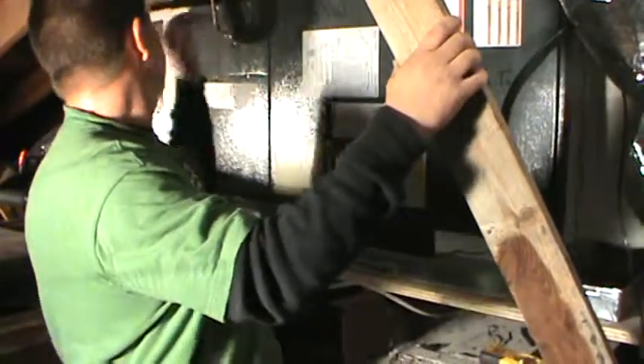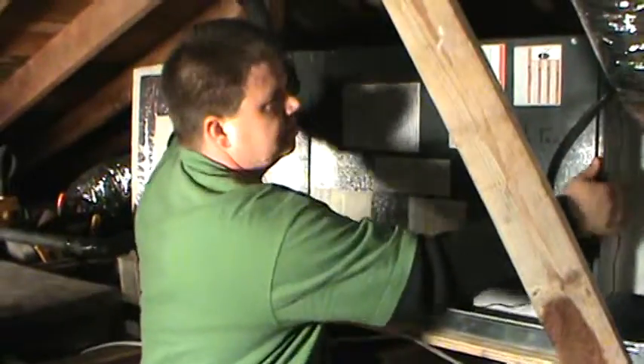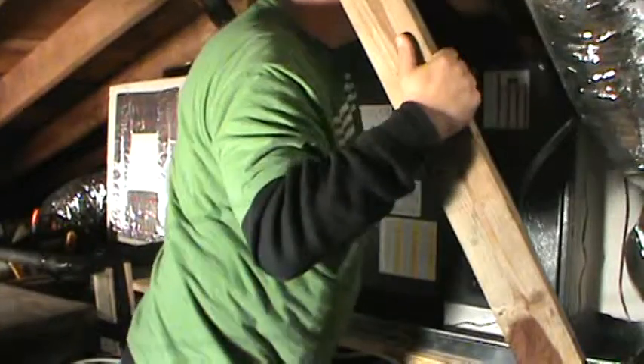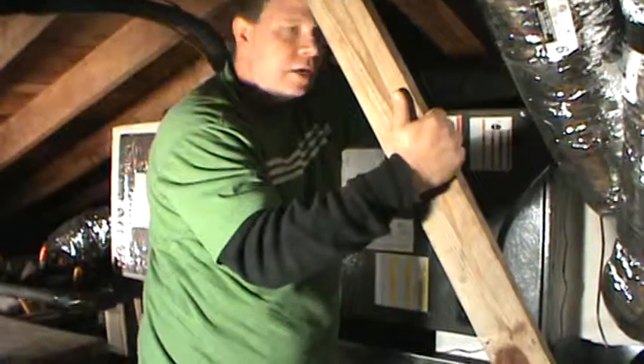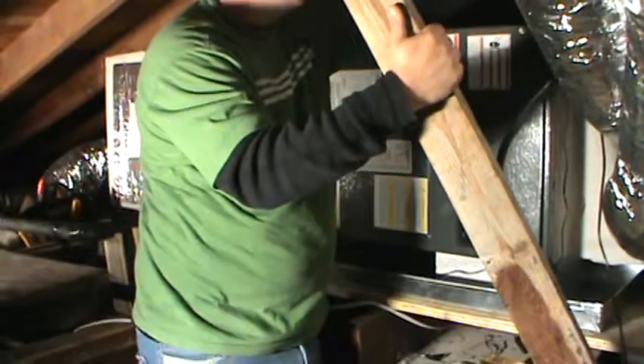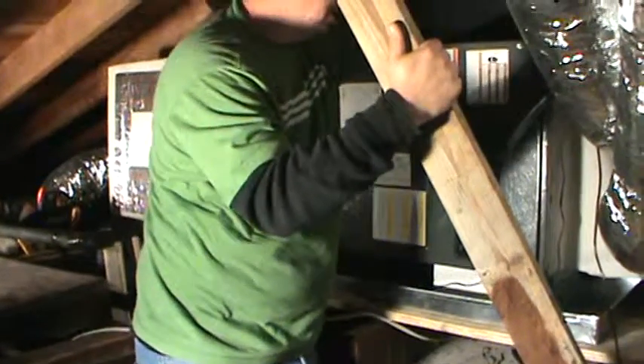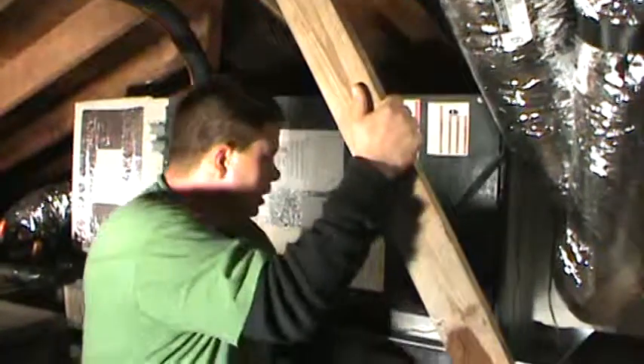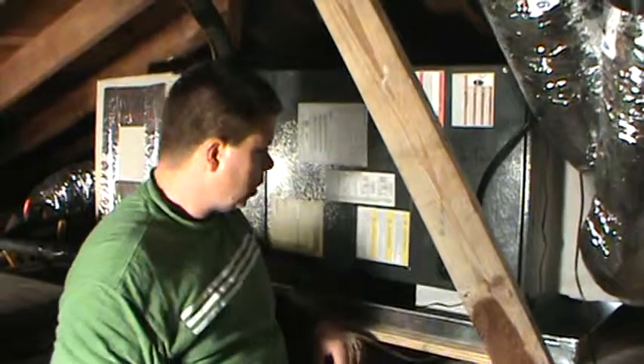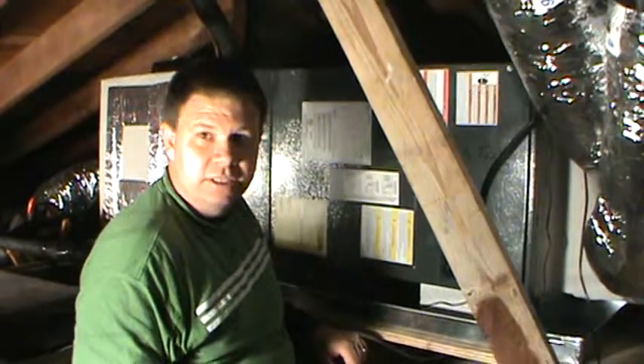Of course, you want to make sure your connections at both sides of the unit are good too. That you don't have any leaking. If so, spray glue, tape that down. If you have some mastic, mesh and mastic is great too. That'll make sure it stays on there. All right, we'll go down and start the unit up, and we'll check the outdoor unit.